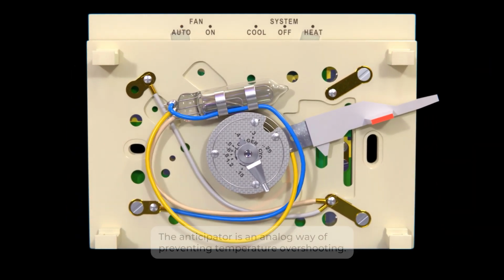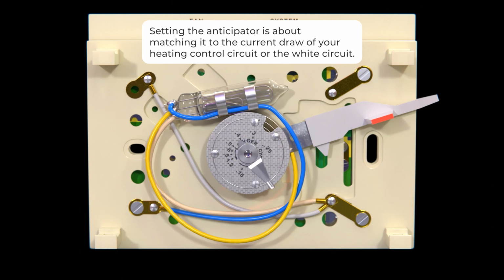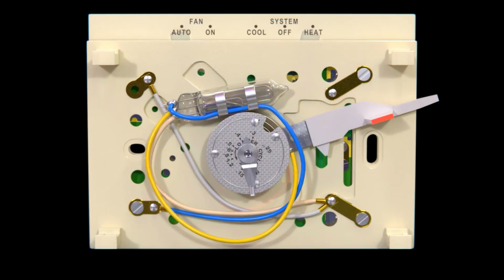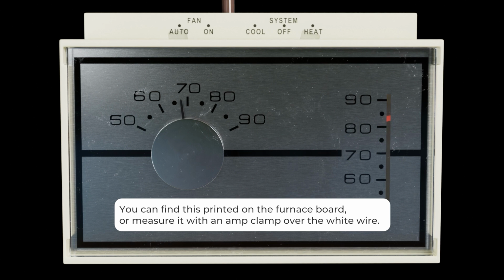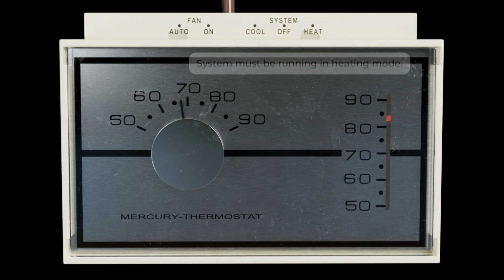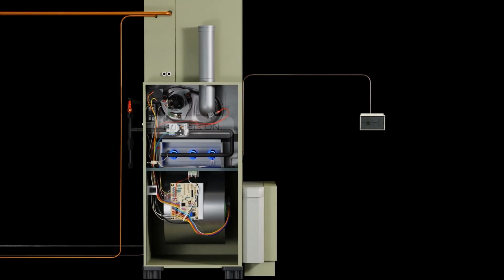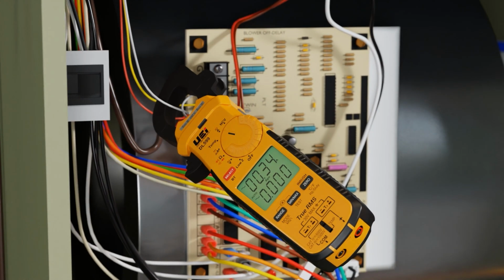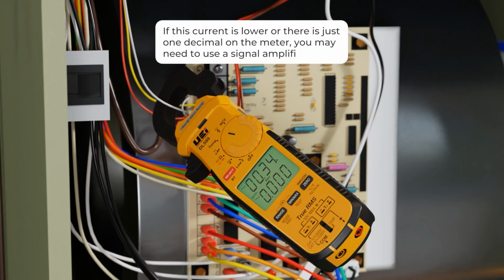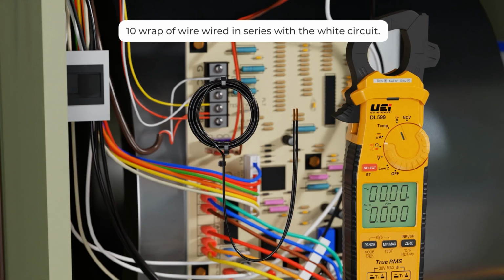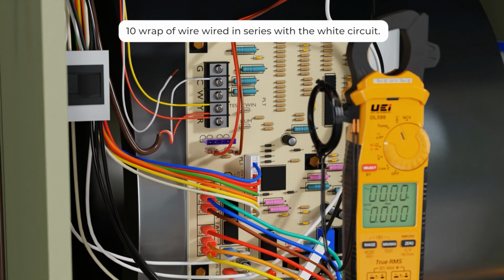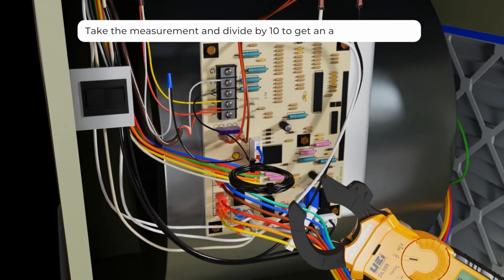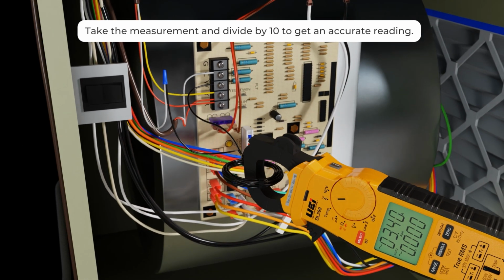temperature overshooting. Setting the anticipator is about matching it to the current draw of your heating control circuit, or the white circuit. You can find this printed on the furnace board, or you can measure it with an amp clamp over the white wire. In cases where this current is lower, you may need to use a signal amplifier. When the current's very low, your meter may not read accurately. You can use a 10 wrap of wire wired in series with the white circuit in order to measure this more accurately. Simply take the measurement and then divide by 10 in order to find what the true current is.